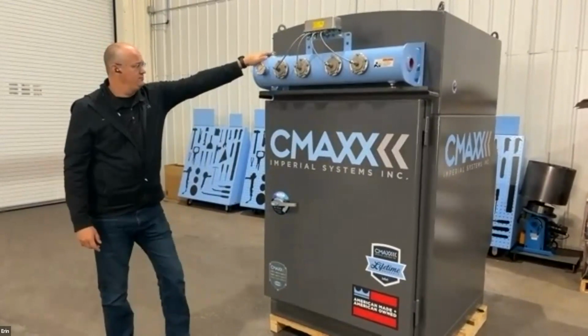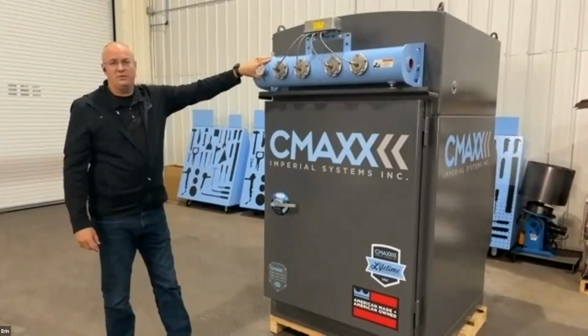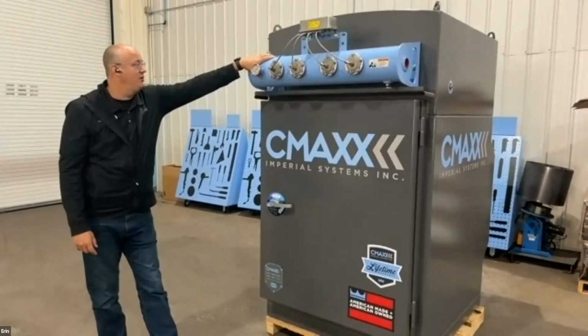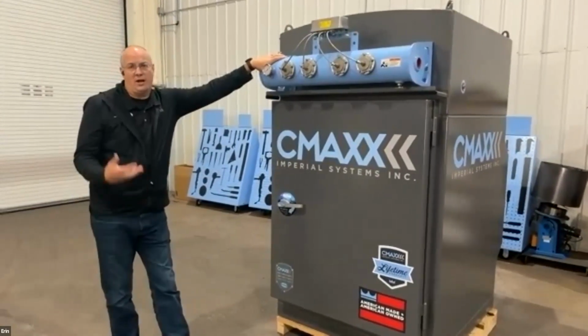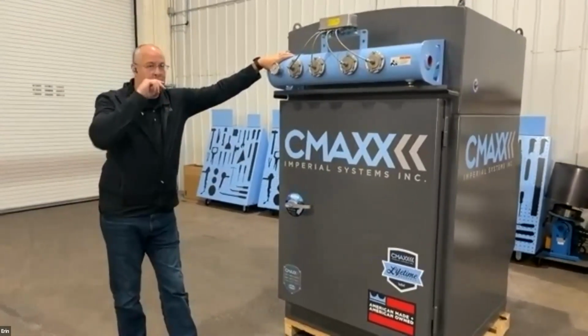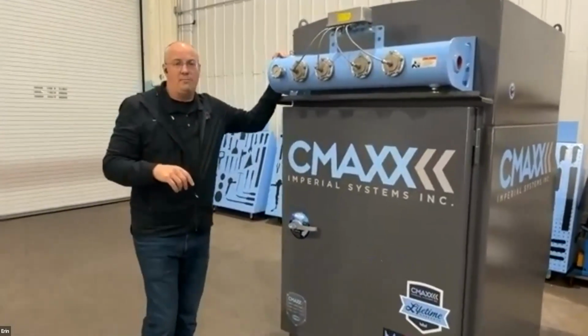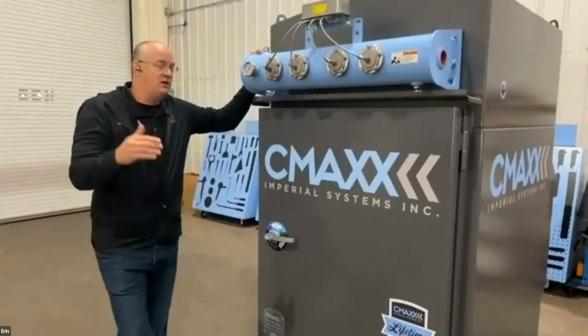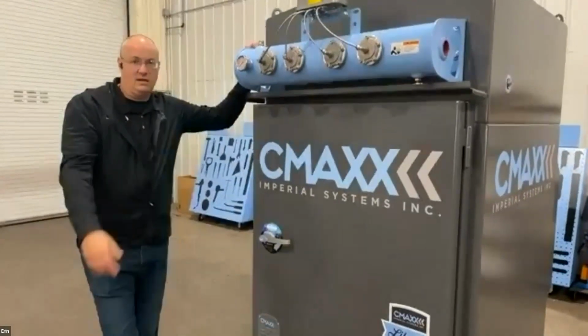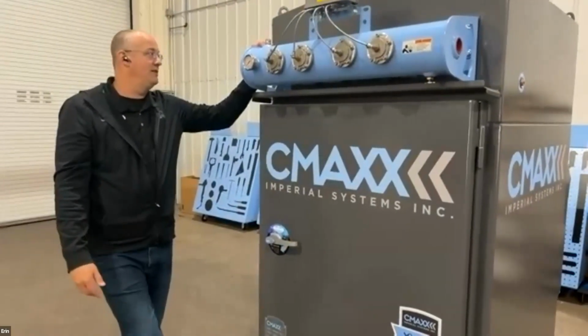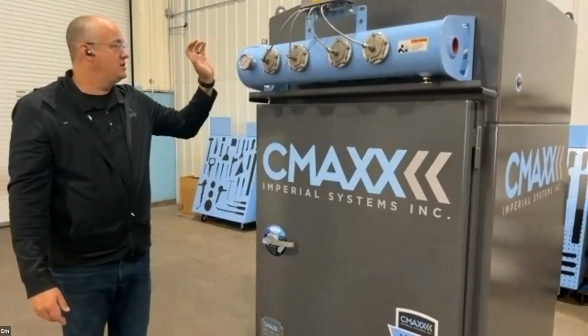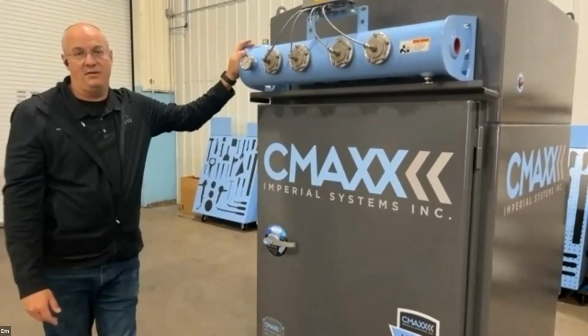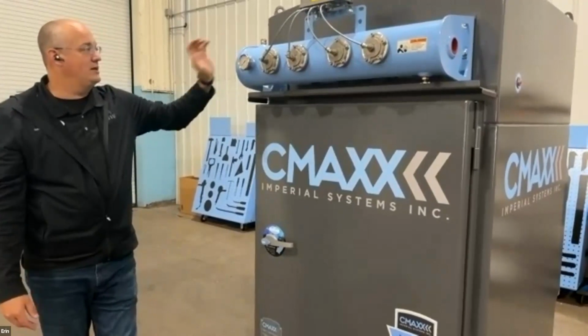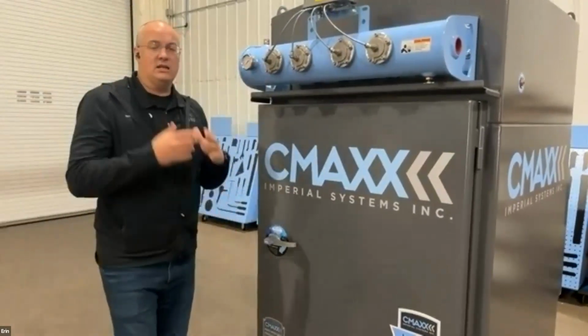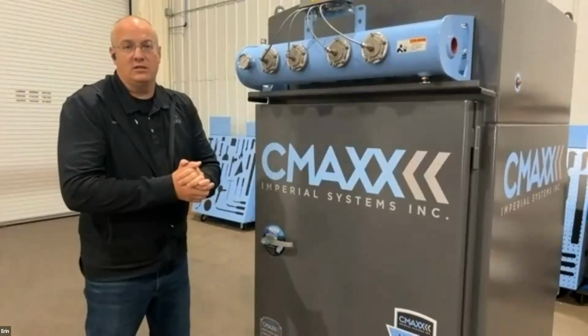We have our header tank with a gauge. Typically, we want to run these at 90 PSI. So when you're talking to people, shop air is an important thing to know because these do consume shop air. So you might need to make sure the compressor is sized for the right size. You want to just take that into consideration whenever you're looking at a collector. This will require 33 SCFM at 90 PSI is what we try to hit each filter with. It's not going to consume that all the time. It's only going to consume it when the filters need cleaned.